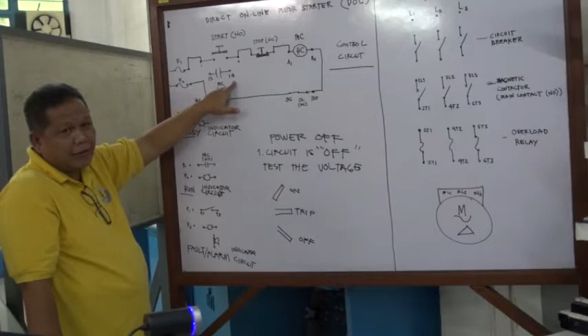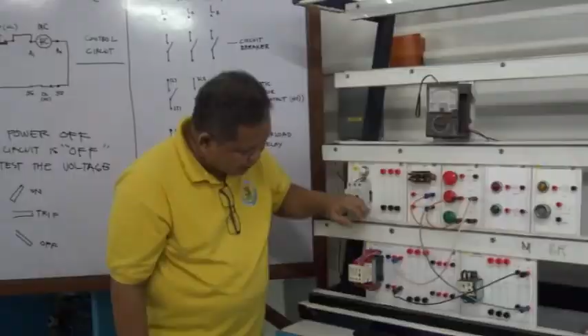So let's finish our first circuit, which is our control circuit. Now we have here a magnetic contactor contact which is normally open. Take note, this is the auxiliary contact of the magnetic contactor, labeled terminal 13 and terminal 14. So if this is our magnetic contactor, this is terminal 13 and this is terminal 14.